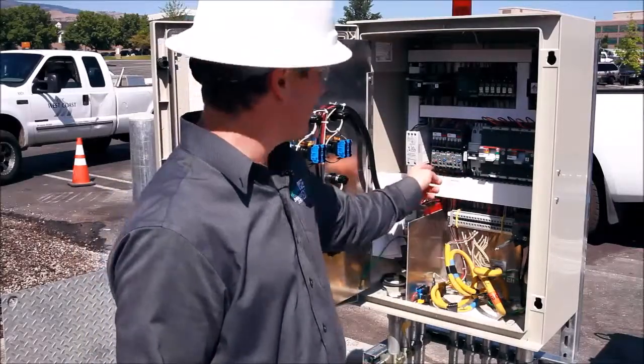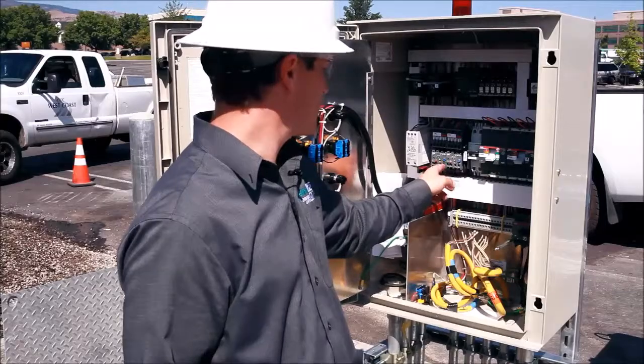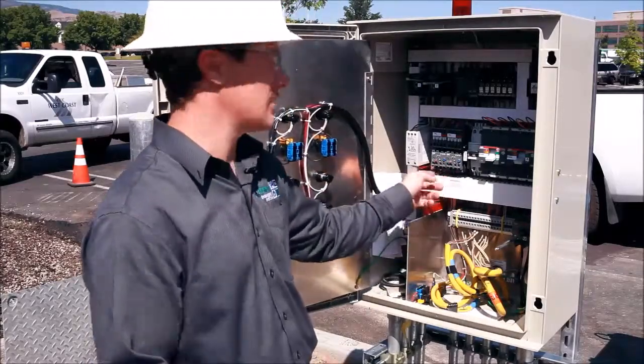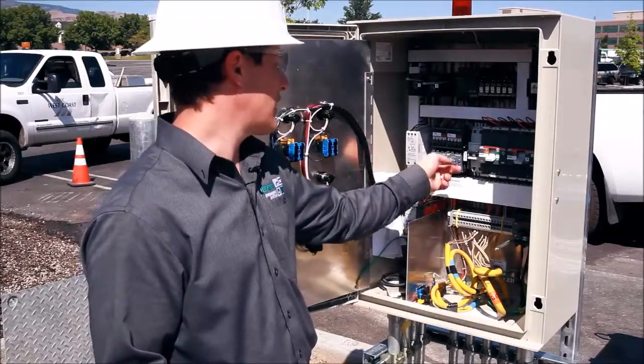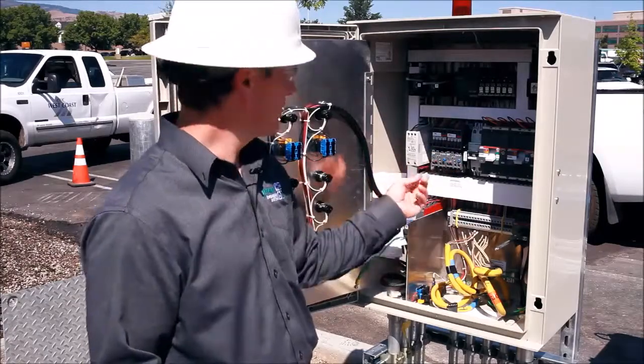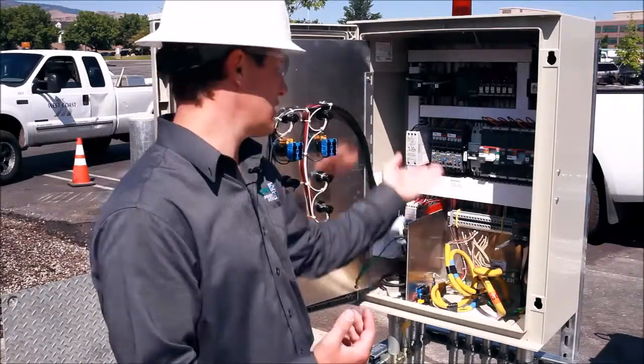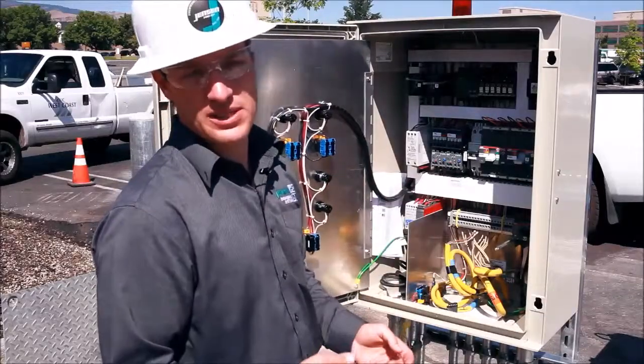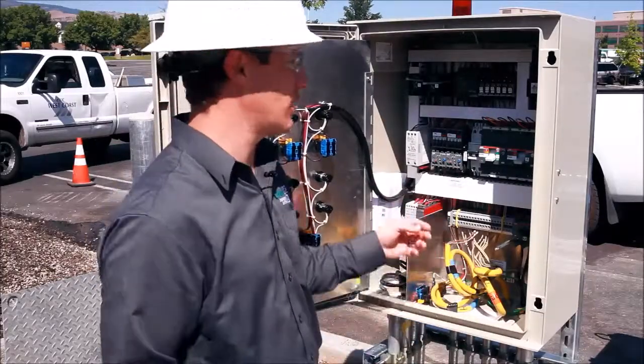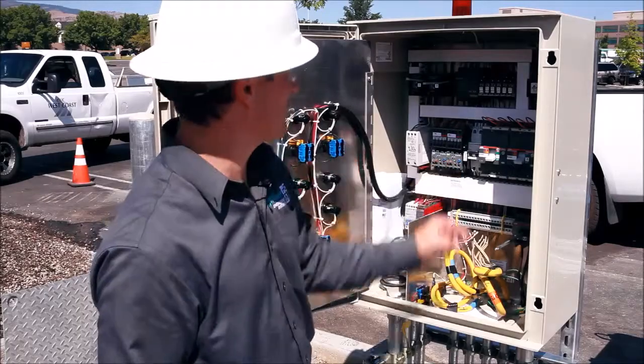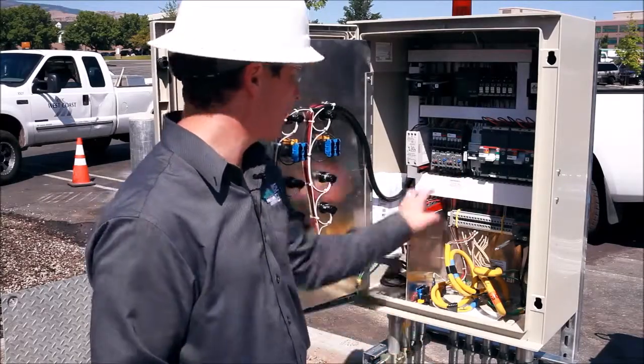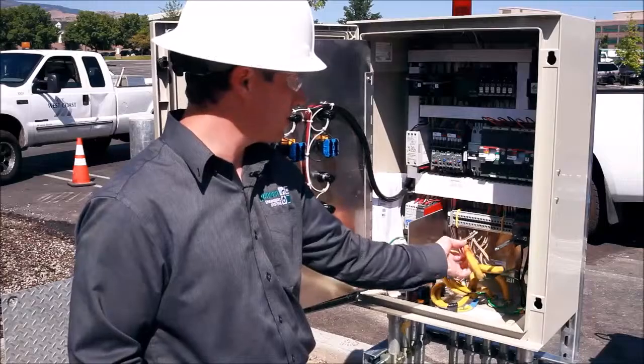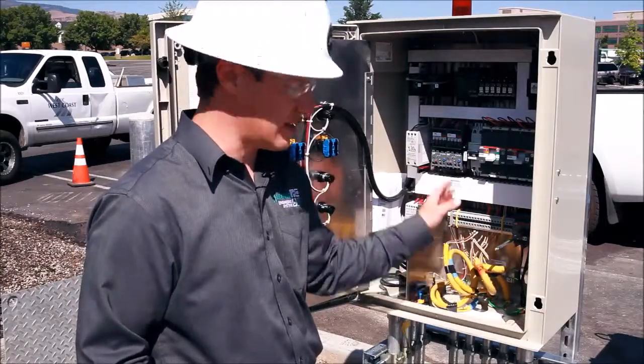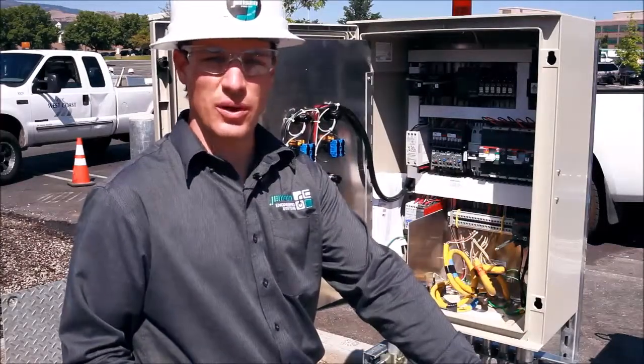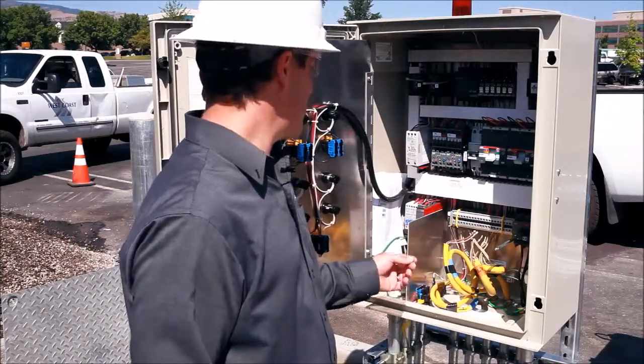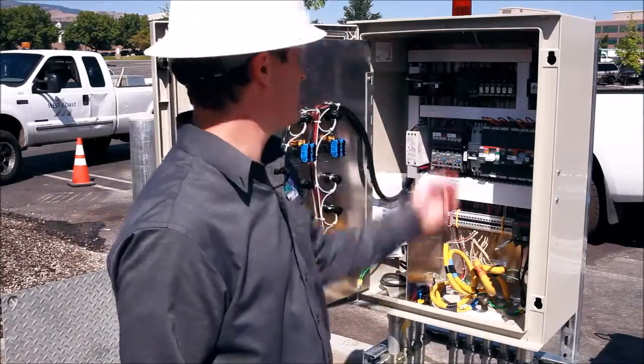In the event that an overload relay was disengaged, the way you would notice is there's a blue dial right here. If that dial switched to manual and popped out, that means that it has disengaged and power can't get through. You have to pull your pump, see what's going on with the pump, remove the object or what have you, then you would depress this blue switch and switch it back to the auto position, and away you go. From there, the power flows down to the pump cables through the terminal blocks, and the power is then passed to the wet well. Some of the other devices we have in here is the Siemens LOGO PLC.